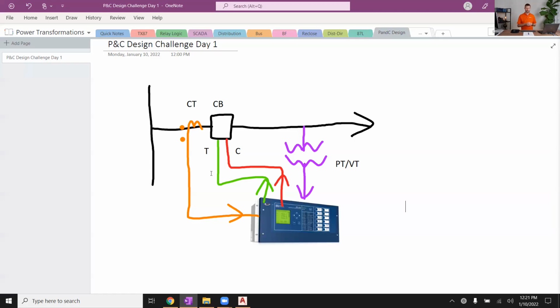This is a sneak peek of what we're going to begin to see on those types of drawings. You should expect to see the primary power system with its layout, its architecture of buses, lines, transformers, both transmission and distribution lines if it's a T to D substation. You should expect to see circuit breakers and other switches, maybe a manual gang operated disconnect switch or a motor operated disconnect switch. You should expect to see your CTs and where they're located and what their polarity dots are, and which CTs are wired to which relays. You should expect to see your PTs and where they're connected to the power system on the primary side and which relays they're wired to. And you should expect to see trip and close signals going from your various relays to your various breakers on the system.